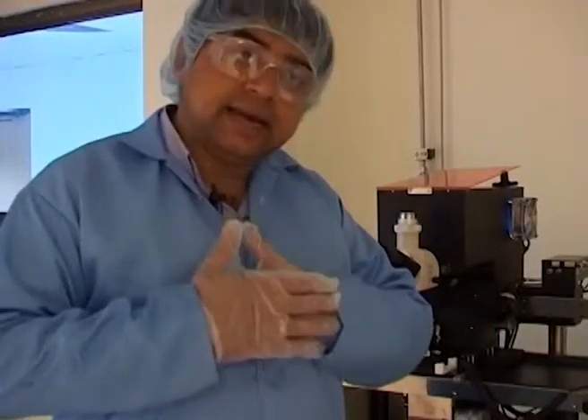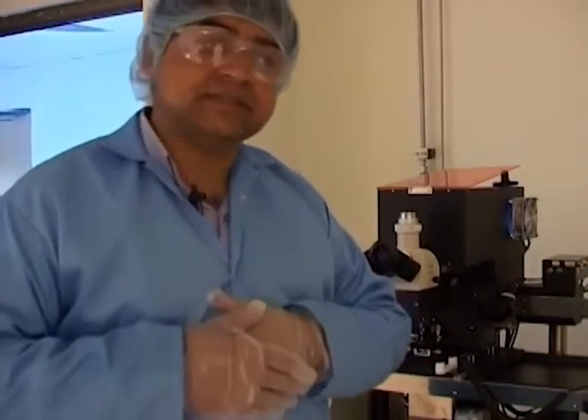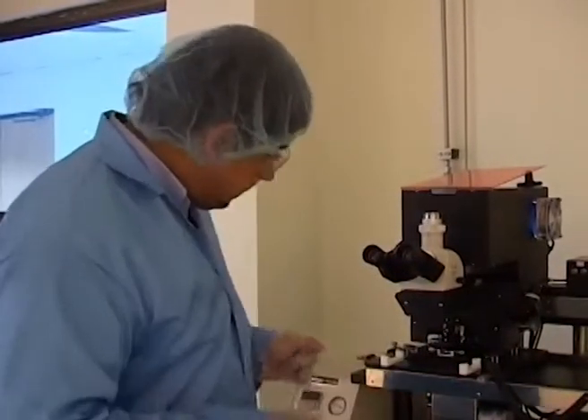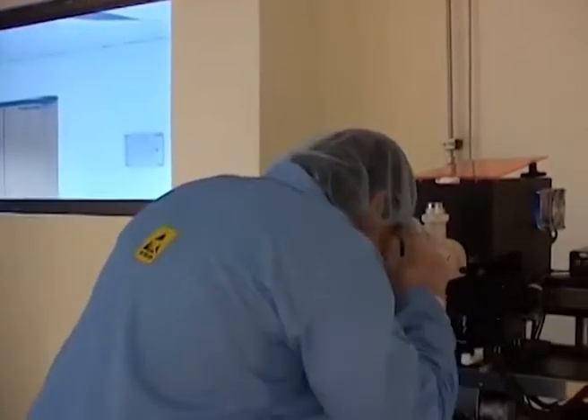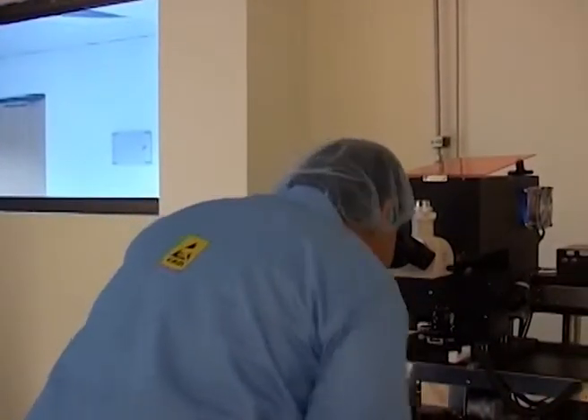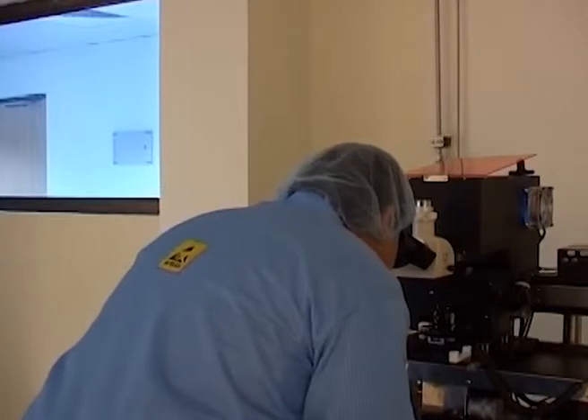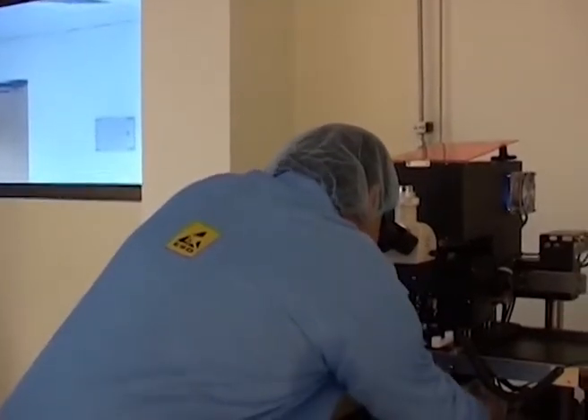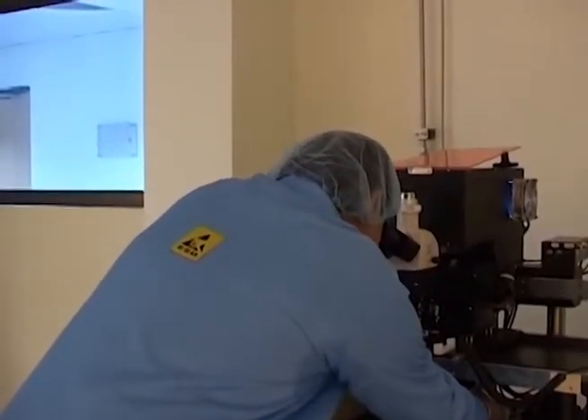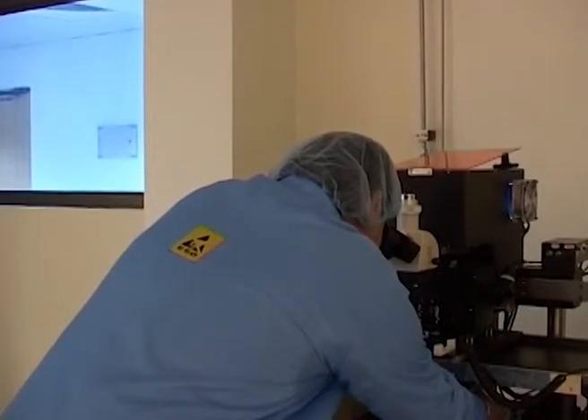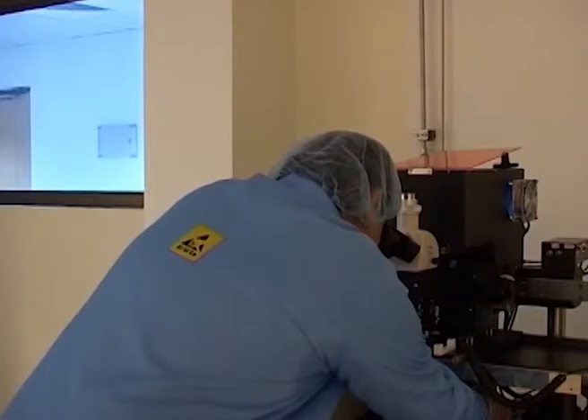Either event is not good for us. We have to just be able to make a close contact without much pressure onto the resist coated surface. One of the reasons why this kind of alignment system is also called a contact aligner. So essentially I would just like to see through this microscope stage and try to find out if the features etcetera are close. I see that there is a little bit of displacement which needs to be done on the Z axis so that the images can be correctly focused.